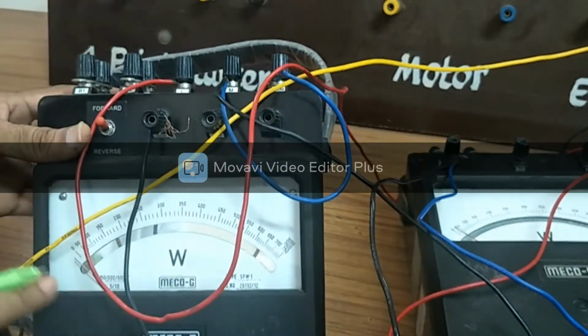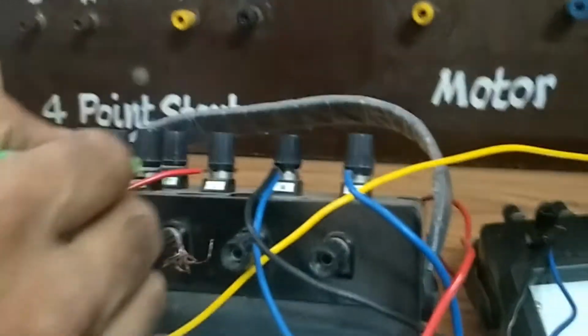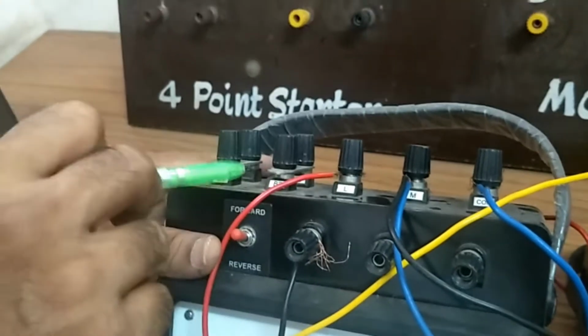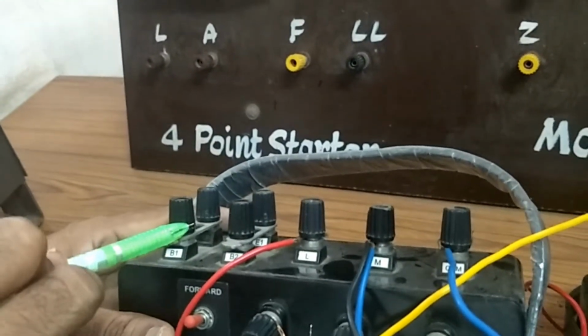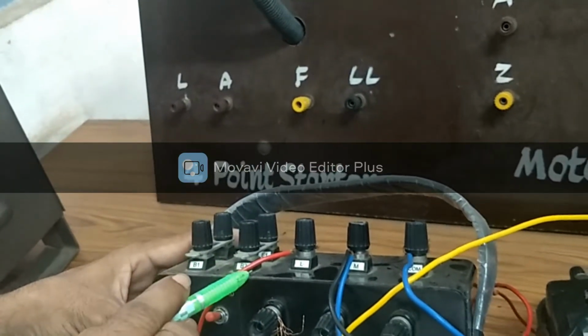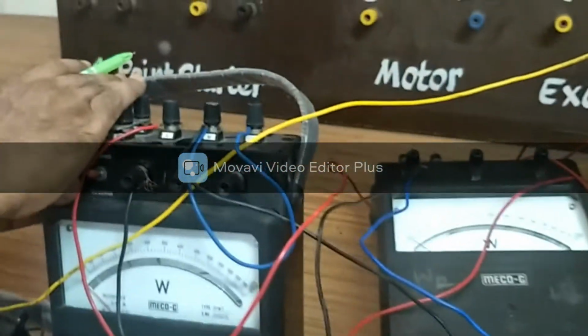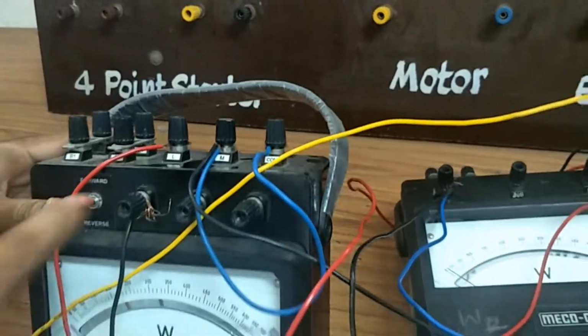Once the connections are as shown here, you must observe the multiplying factor of the 2 wattmeters. This is very important. As I said, there are two types of current ratings in the wattmeters: 5 amps and 10 amps. If you connect B1 and E1, and B2 and E2, as shown in this way, it appears to be a parallel connection. This is for the full current rating, 10 amps. Instead, if you connect only these two terminals, B1 and B2, then it is for 5 amperes. Since we are using the 0 to 10 amps range, definitely this should be a parallel connection as shown in this diagram. Now this is at 10 amps.